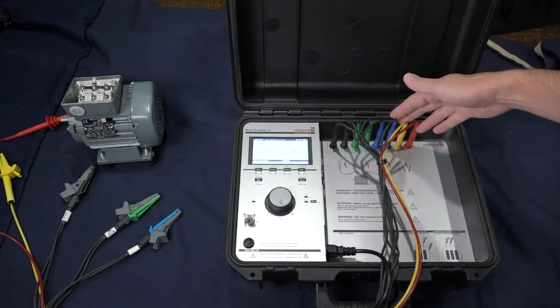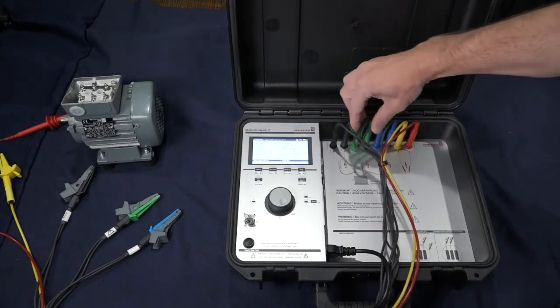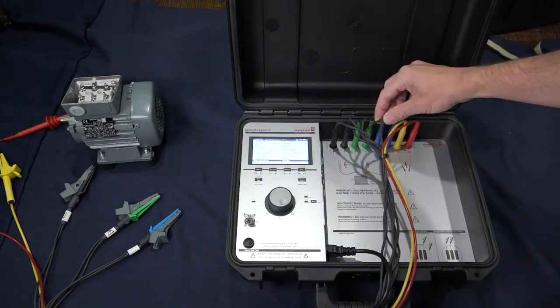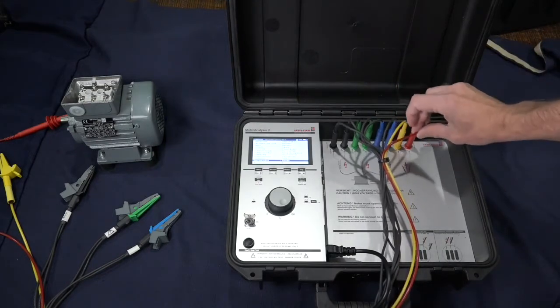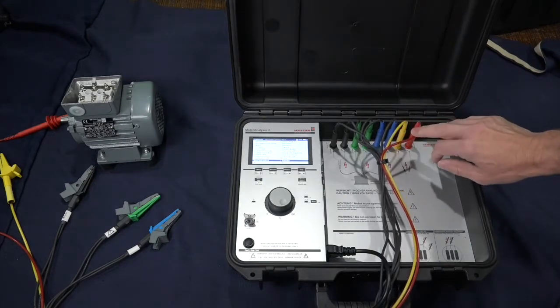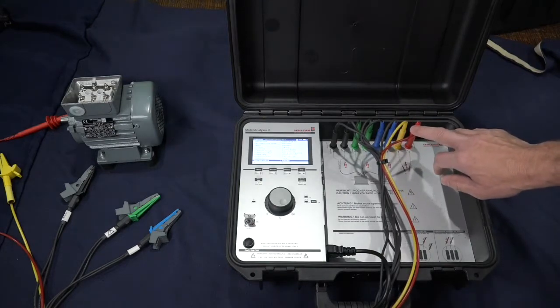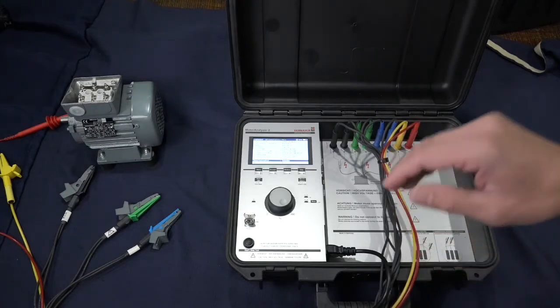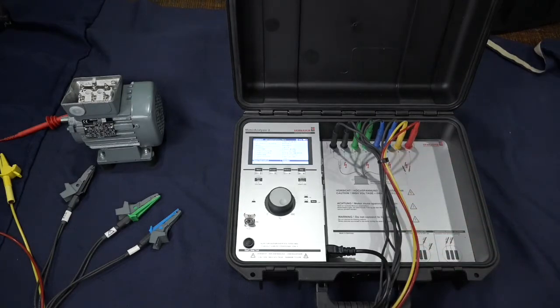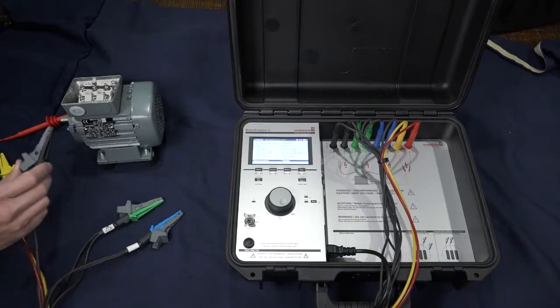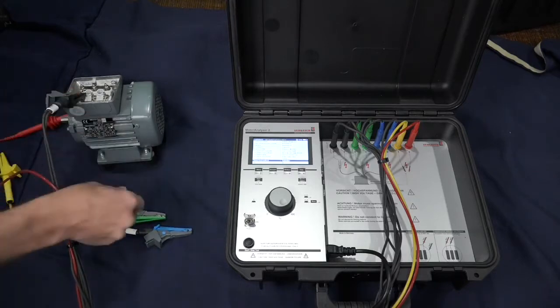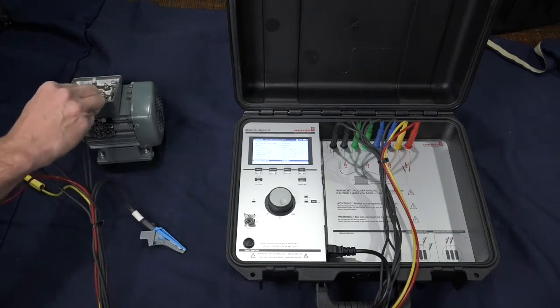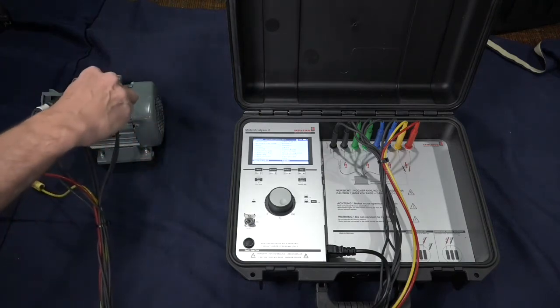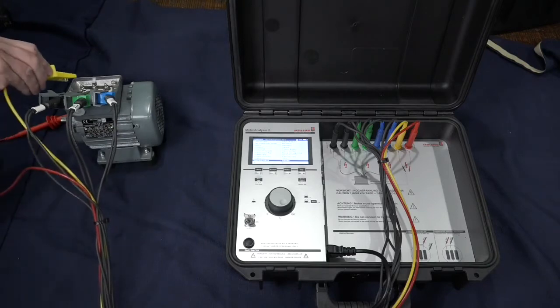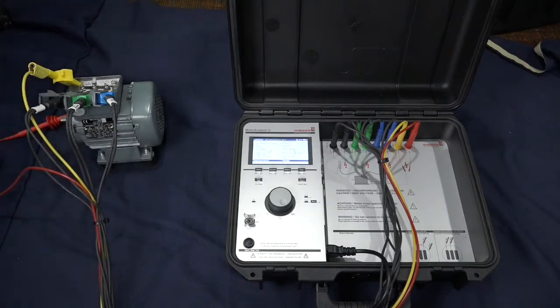There are 8 test leads total, 2 for lead 1, 2 for lead 2, and 2 for lead 3. The yellow one here is a ground, and the red one is a separate dedicated 6 kV DC high pot test cable. So let's connect our stator over here. Here is lead 1 going to phase A of the stator, lead 2 to phase B, lead 3 to phase C, and our yellow ground. And with that, we have our stator connected.